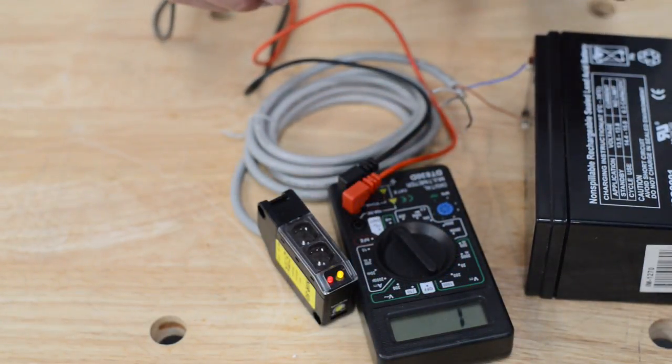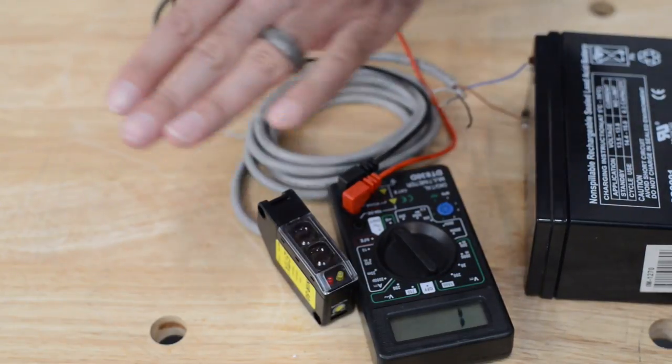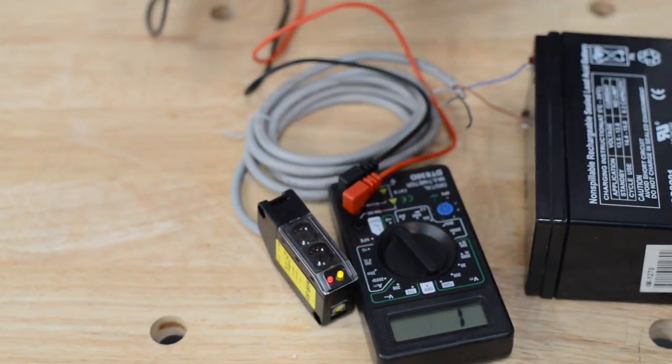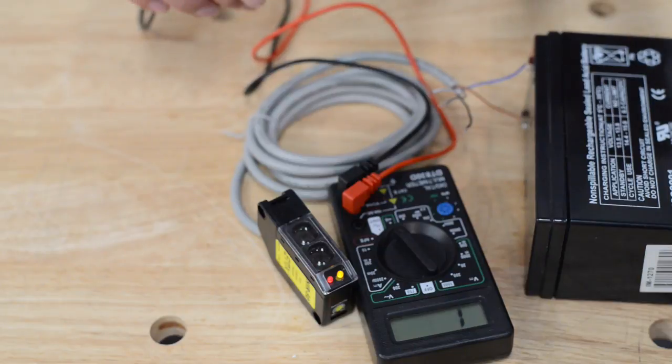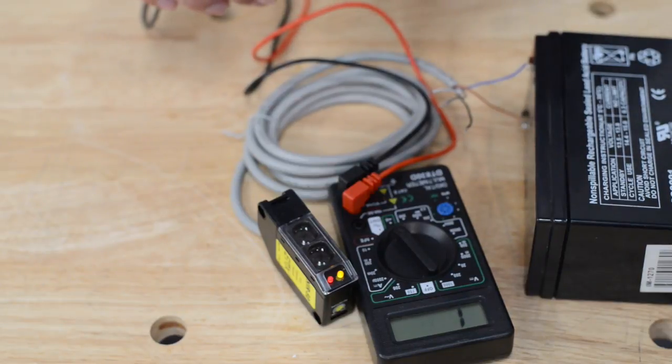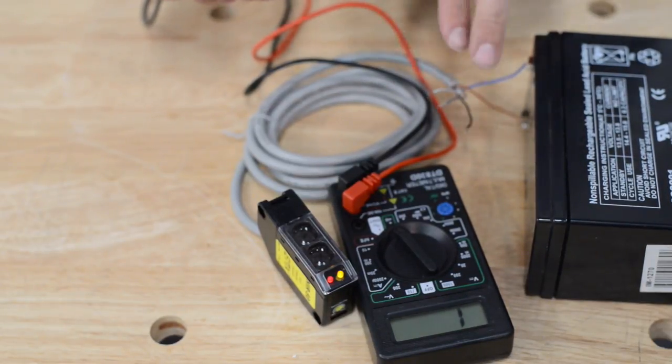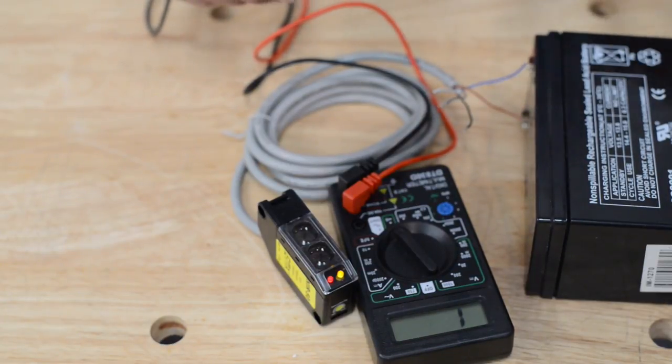So now that we have it powered up, we know the beam is working. I can trip the beam. I can hear an audible click. That audible click is the relay clicking inside. It's a working beam. We have three wires left. We're going to determine which one's normally open, which one's normally closed, and which one's common.